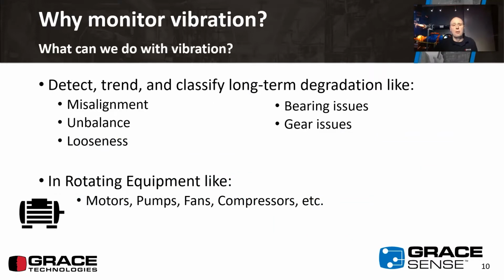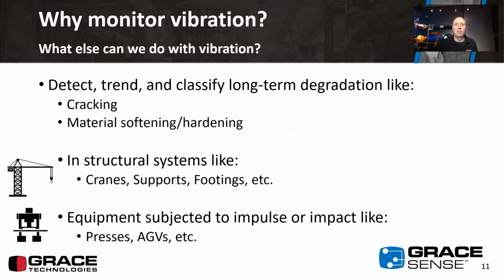So once we've got a monitoring system in place, what can we do with it? We can leverage that vibration monitoring system to detect, trend, and classify different types of degradation—specifically things like misalignment, unbalance, looseness, and issues with bearings or gears. These can be applied in a lot of different ways on different types of assets, from motors to pumps to fans to compressors and the like.